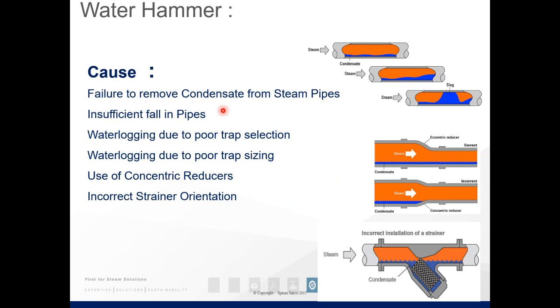And the use of concentric reducers. This image here is the correct installation of an eccentric reducer, where you're going from a larger pipe to a smaller one. If you use a concentric reducer in this direction, you can have a buildup of condensate there. If steam was coming this way, you wouldn't have the problem. But here you're creating a step up, a point for condensate to build up.